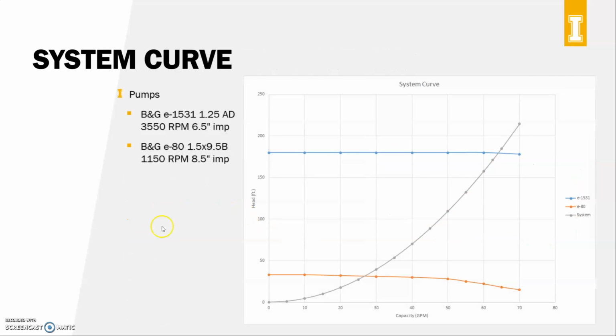Now, our system curve, this is what I was talking about with the main pump not operating at super optimal efficiency. Because we're operating in the early part of the curve, it's almost just barely curved here at the very end. But this pump is a good example for the cost of what will provide the flow that we need. Now, our cold water pump down here obviously is a much lower head, and for that reason, it is operating at a more optimal point in its curve. Now, fortunately, we figured out that this will provide all of the water that we need. We just chose this pump because we believe for the cost to pumping ability, we thought this was the best deal.